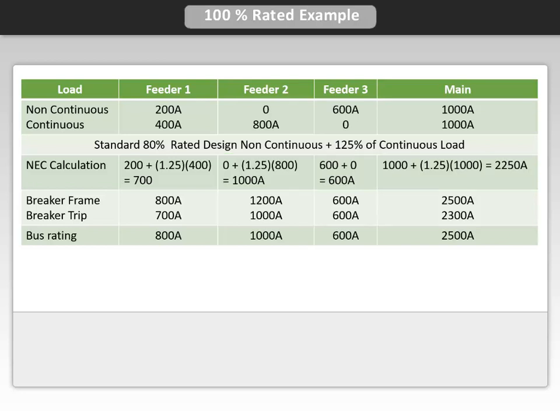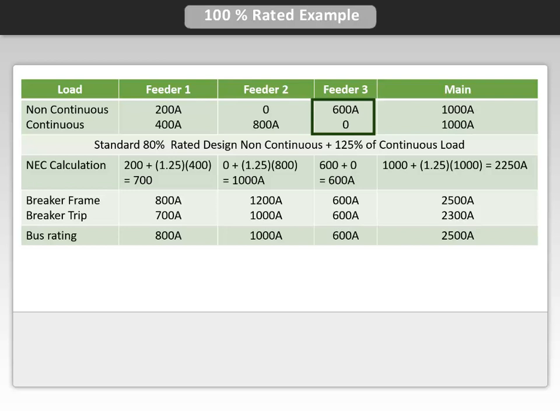Again, since 1,000 amps is not a standard rating, we must use a 1,200 amp frame with a 1,000 amp trip unit. Feeder number 3 has a 600 amp non-continuous load and therefore does not have to be derated.